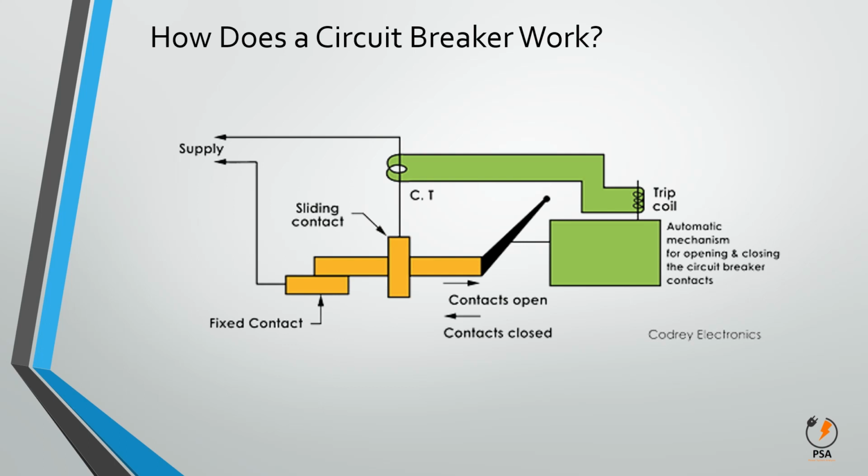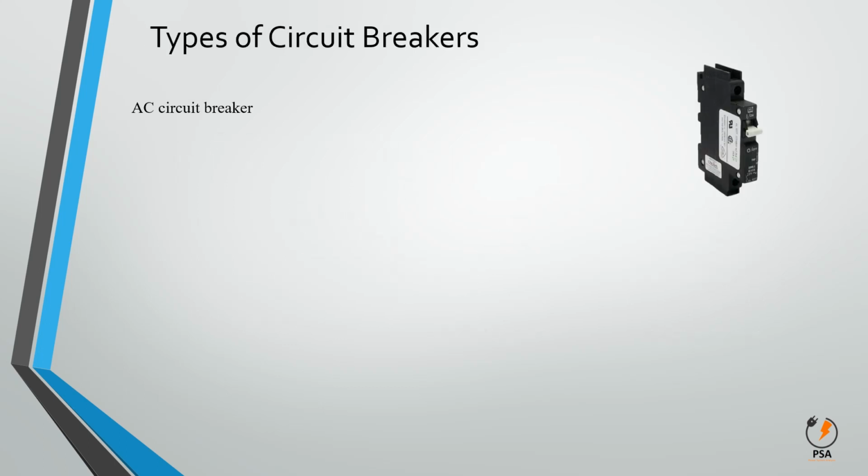After one operating cycle of the circuit breaker, all of the stored energy is released, and thus the potential energy is again stored in the circuit breaker operating mechanism by using a spring charging motor, air compressor, or other means. Let's introduce you to different types of circuit breakers.